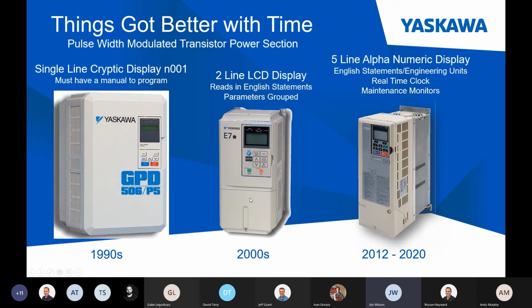In the 2000s, the E7 drive came out. This was the first drive in the marketplace specifically designed for commercial HVAC. It wasn't just an industrial drive with somebody waving a wand over it. It was programmed from the ground up for commercial HVAC. It only had a 2-line LCD display, but it read English statements, and we grouped the parameters, so if you needed to adjust motor parameters, they were all together in that group. We've actually never changed that grouping.